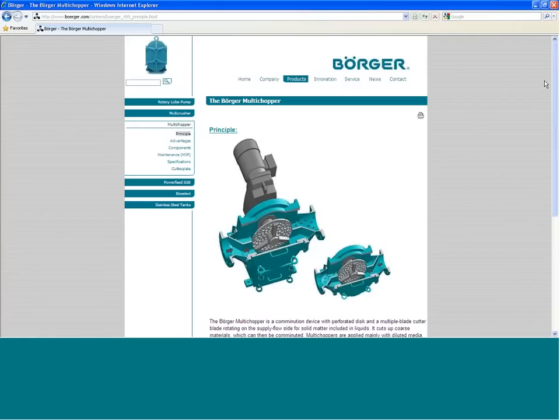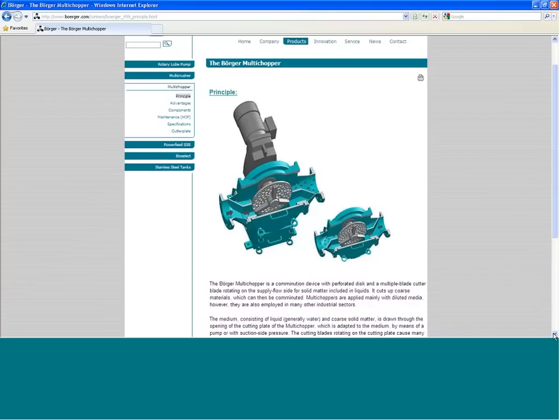If you're looking from above on the unit, basically the flanges are divided, and you can orientate the flange to dictate your suction and discharge. But the large arrows dictate your incoming product, so it comes in basically there on the left-hand side. It's forced past those three rotating knives and then passed through the stationary plate. So that plate is available in different configurations that will determine the throughput size of your product. So essentially, we've got a very tight shearing action that's occurring there. And we can run this unit at multiple speeds, too, depending on your application, your product, your throughput. So we'll work with the end user. But as it's passed the rotating knives and stationary plate, it comes out in a reduced form. And you can see, it's bidirectional as well, so it's very flexible out in the field.